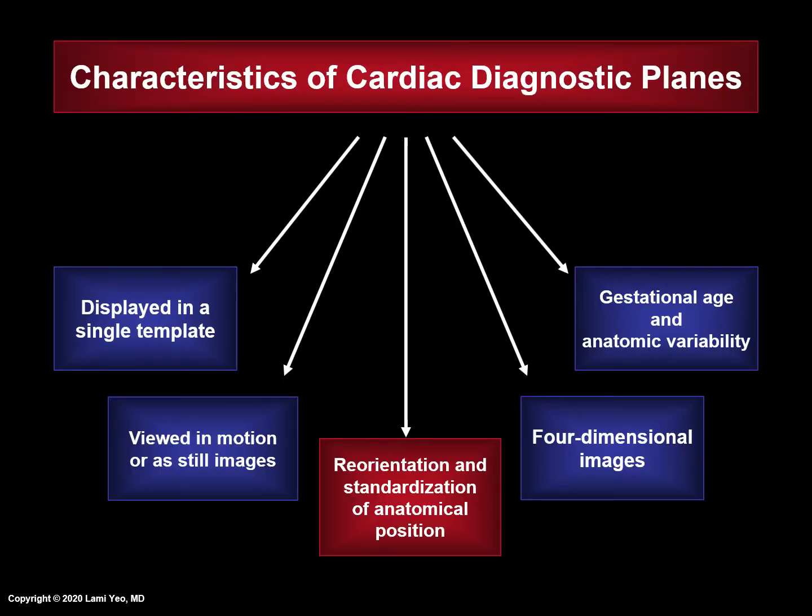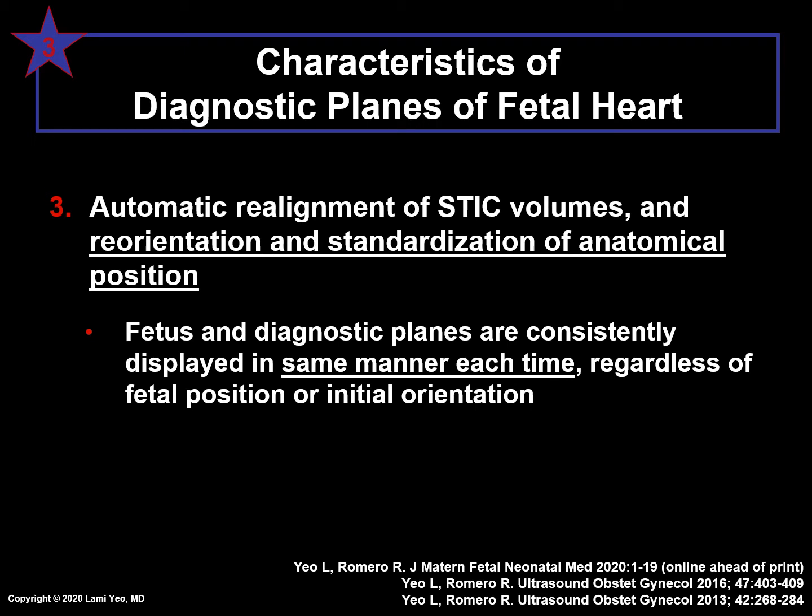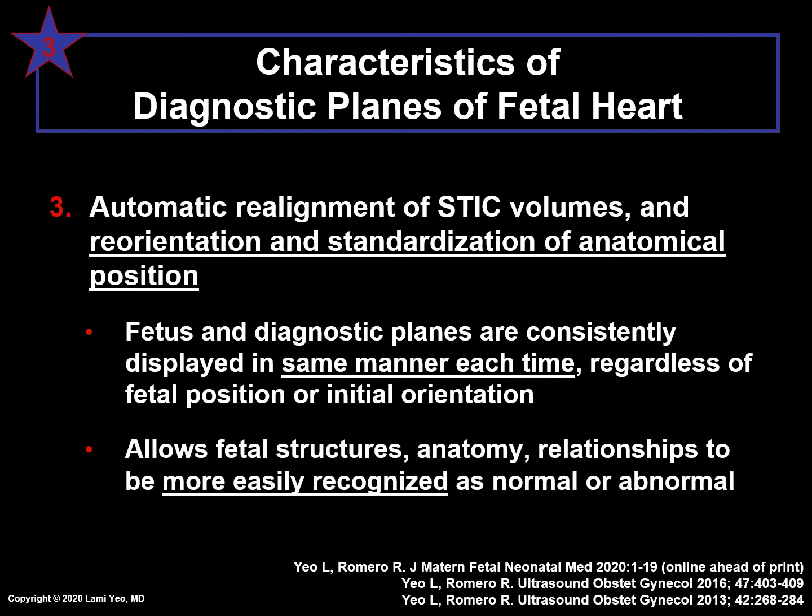The third characteristic of the cardiac diagnostic planes is that through intelligent navigation technology, FINE performs automatic realignment of STIC or spatiotemporal image correlation volumes, as well as reorientation and standardization of the anatomical position. Specifically, the fetus and diagnostic planes are consistently displayed in the same manner each time, regardless of the fetal position or initial orientation. This allows fetal structures, anatomy, and relationships to be more easily recognized as normal or abnormal.